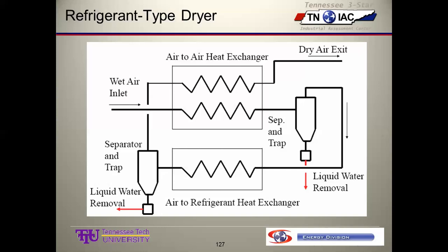Okay, with all that being said, let's take a look at this simple schematic of this refrigerated air dryer. Over here, this is the inlet to the dryer, coming out of the discharge of the compressor. The spec on this is probably, in nominal terms, 100 degrees Fahrenheit and 100 psi. Could be a little higher, could be a little lower on the temperature. They don't like it to be much higher than 100. It'll start to derate the capacity of this thing. But the first thing it does, it goes through this heat exchanger.